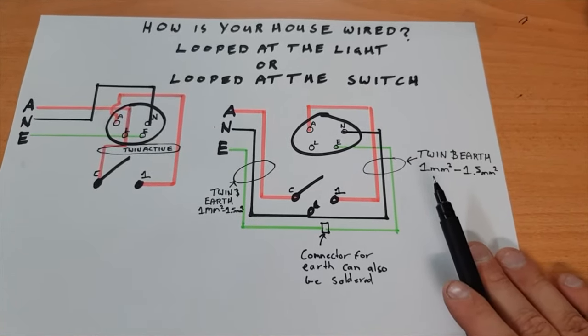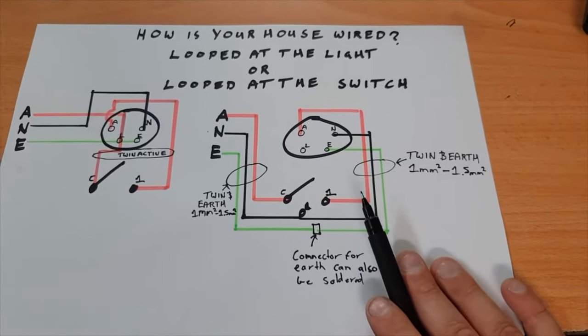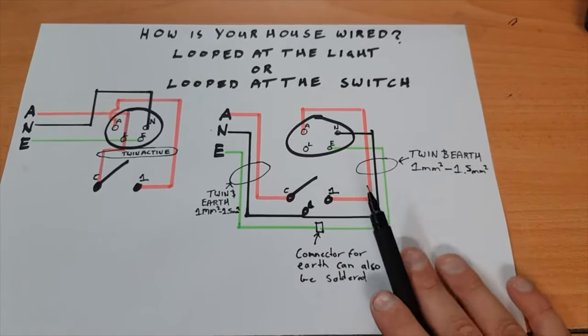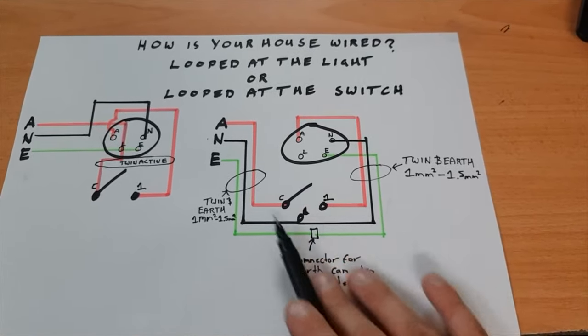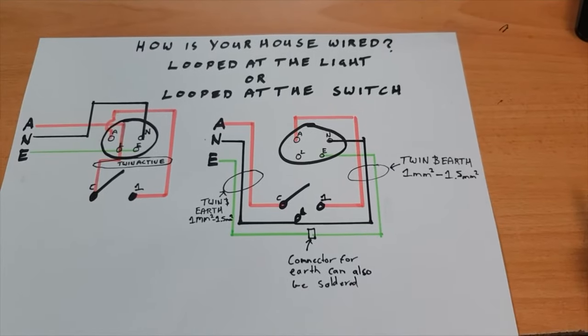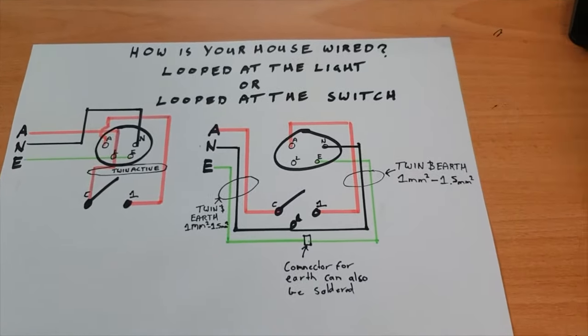So from the 90s onwards, let's say, this is looped at the switch. It's looped at the switch because the power goes to the switch first, not the light. So then you can from this switch just daisy chain all to other switches and then up from those switches to your other lights and so on and so forth.